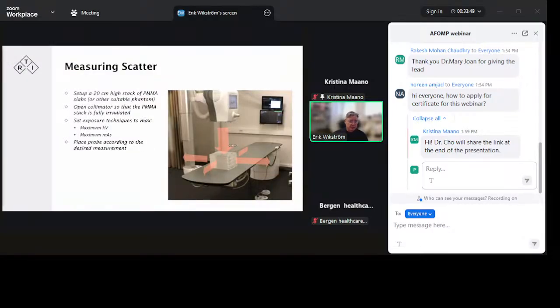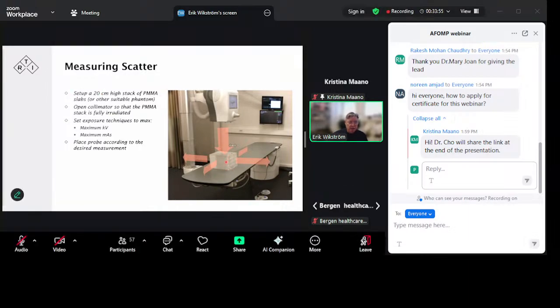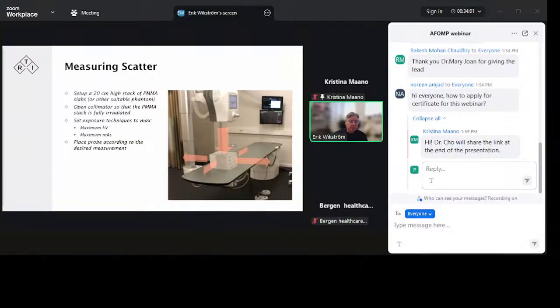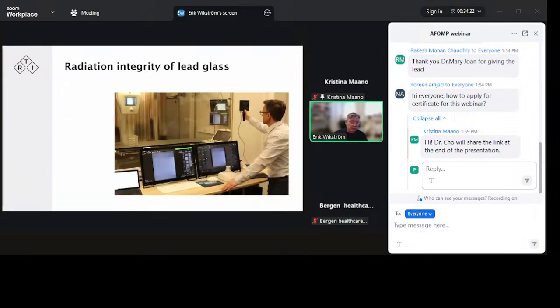So in most cases, what we do is we set up a stack of 20 centimeters high, a stack of PMMA slabs or other suitable phantoms for this, but this is a standard way of doing it. You open the collimator to fully irradiate the stack of PMMA, and again set the technique to maximum kV or maximum mAs, and then we may place the probe according to the measurements that we want to achieve. And that could be looking at the integrity of the lead glass into the control room. Is the attenuation of the lead glass proper?